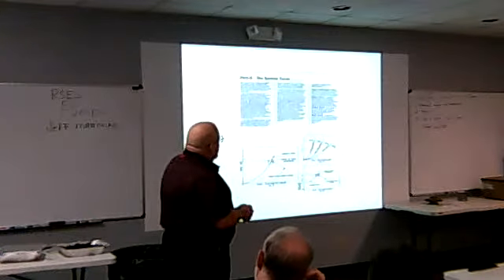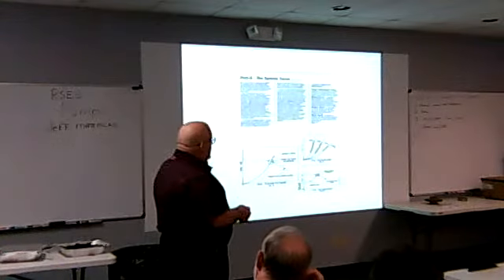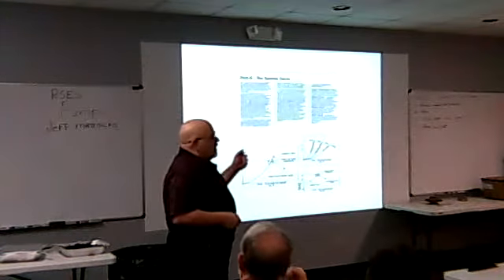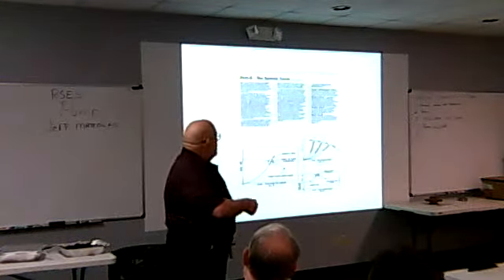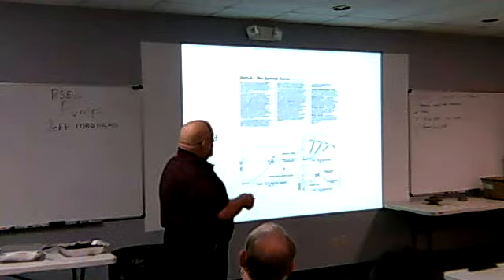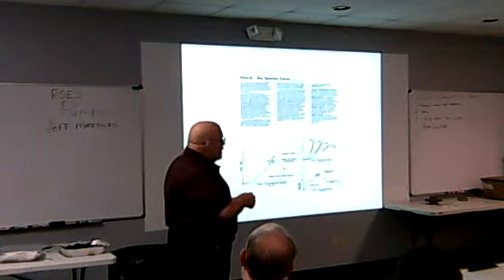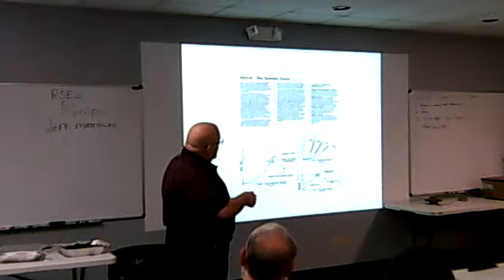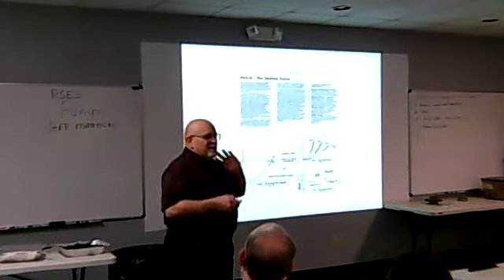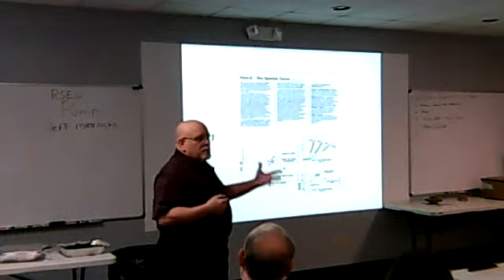This is just a curve right here. I showed you the different curves. Like I said, if I have an open system and I throttle the discharge valve in a pump, this is the beauty of hydronics, plus or minus 50%. If I over design the pump and I run out here, I can throttle that pump down, add head to the pump, and it's going to move itself back and reduce the flow. So if I'm overflowing, by choking down the pump I'm adding head and the curve is going to back up just like this to the flow I want. I designed for here and I wound up here. If I throttle it, I can get to there. I'm wasting energy. That's why VFDs and such are important, but just for the simple concepts. Okay.